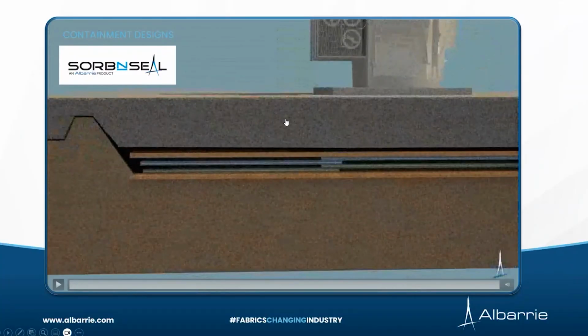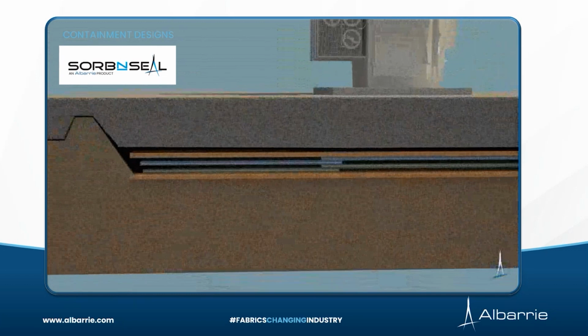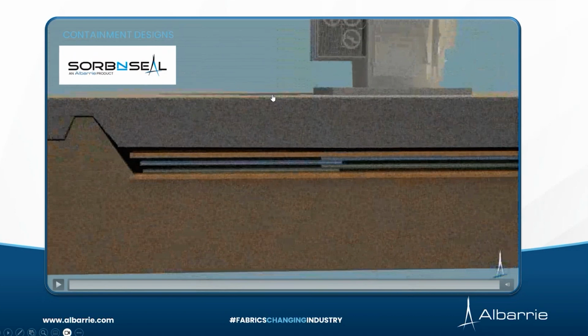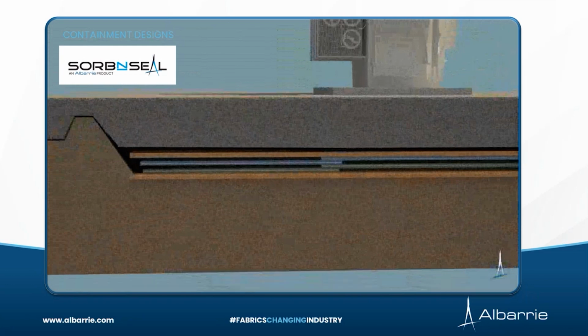So if you had a spill, a catastrophic spill, or even a larger spill, what you would do is you would dig a V channel into the stones in the area where the discoloration can be seen from the leak. And then you would suck up all the free liquid, okay? And then you would keep digging until you reach the bottom layer here, or the oil mat, or you don't see any more oil, whichever one comes first, and you would stop there.